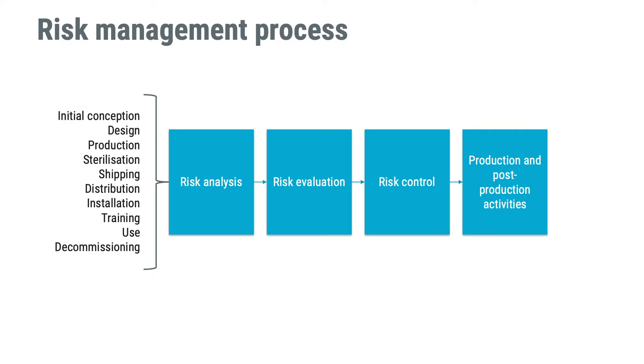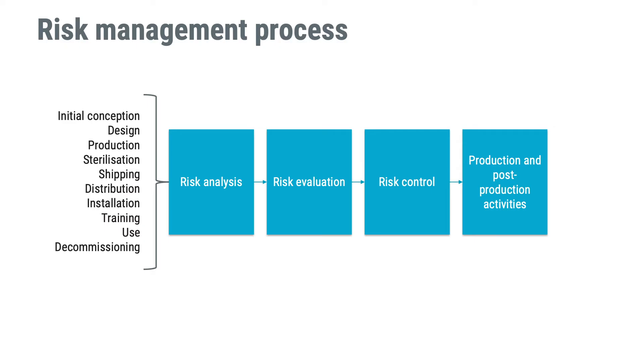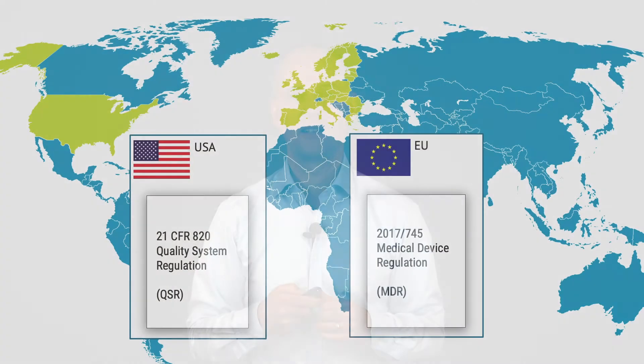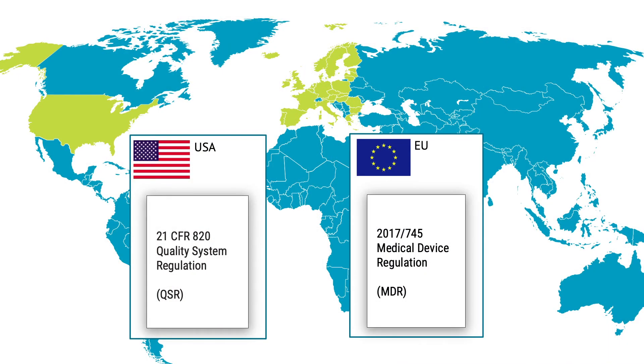Please note that your medical device may very well have different life cycle phases than in this example. The requirement on addressing risks from all life cycle phases also means that if you provide services, components, or materials to a medical device manufacturer, you should also be engaged in risk management in one way or another. Working with risk management is required in the quality system regulation that applies if you want to sell your medical devices to the US, and also required in the medical device regulation for the EU.